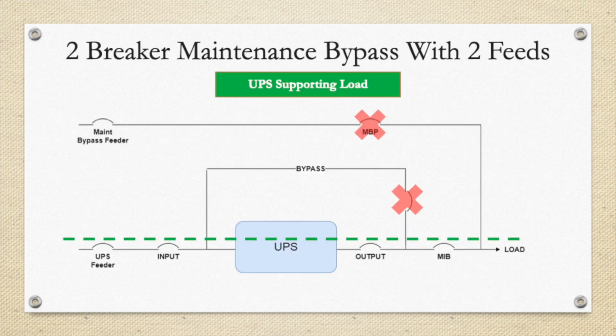We go to the next drawing, and what we're showing is a 2-breaker maintenance bypass with 2 feeders. So if the UPS installation is afforded 2 separate feeder breakers, we would recommend feeding the UPS from 1 feed and feeding the maintenance bypass from a 2nd feed. First drawing showing the UPS online. So the UPS feeder is on, the MIB is on, the MBP is off. Again, before we can go to maintenance bypass, we have to transfer this system to internal bypass.